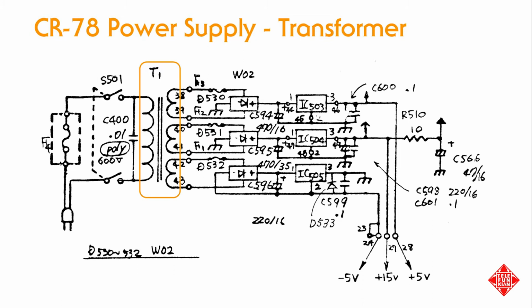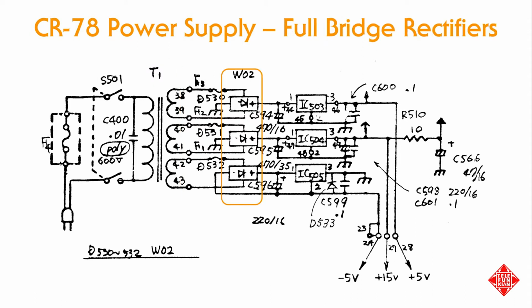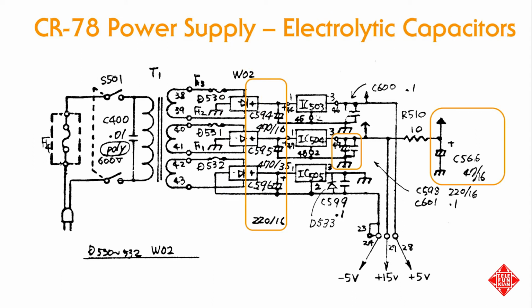Each of these transformers have three independent secondary windings that provide independent AC sources that provide power to the three main DC rails used in the instrument. After passing through independent fuses, each AC source is sent to an integrated full-bridge rectifier converting the AC to DC power. The rectified DC power is then smoothed by 470 or 220 microfarad electrolytic capacitors before being regulated to maintain the target 5, 15, and negative 5 volts.